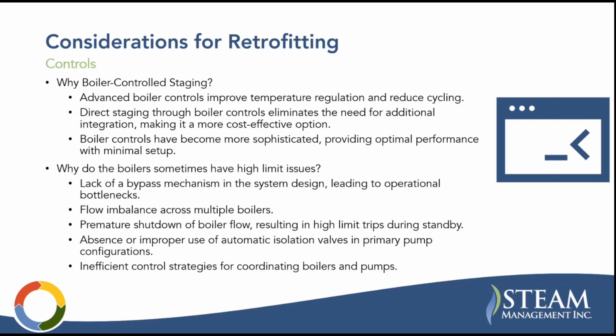It's often because of a lack of a bypass mechanism in the system design. It could be flow imbalance across multiple boilers. It could be premature shutdown of boiler flow, so the boiler is still heating that water without flowing. It could be absence or improper use of the isolation valves, which I mentioned. And inefficient control strategies for coordinating the boilers and pumps. So all of these are kind of arguments for letting the boiler control as much as possible so that these are already kind of accounted for.